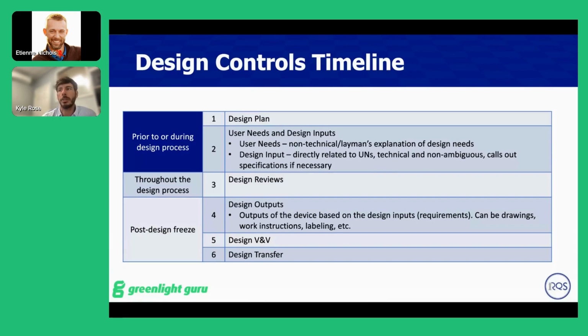This specifically ties to startup companies that are doing this for the first time and have not worked in a medical device quality system in the past and are starting from scratch. With more established, bigger companies, the majority of the time you will have to have these things in place before you can even start working on a project. You'll have to have a design plan and user needs and a project roadmap, all of those things before you can start. But this is specifically for startups and the ones that ask pretty frequently, when do we start design control? How late is too late? All of that type of stuff. So the product before moving to design freeze is really where you want to start with these design plan, user need, and design input activities. I wouldn't go any further before starting that formal documentation.